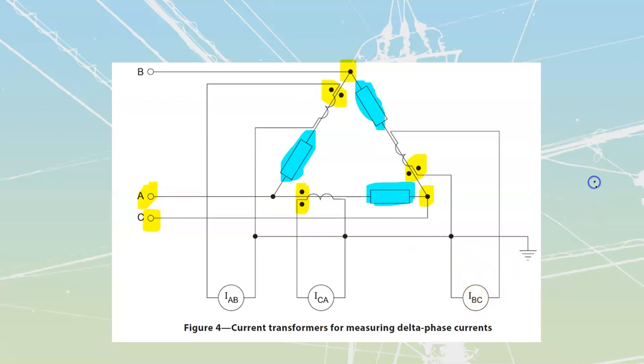This doesn't make any difference to us that it's connected into a Y type of configuration, because if I look at the individual meter loop, it's just reading what's inside here, and we're not even looking at voltage. Voltage is the thing that changes from delta to Y when we're going across. At this point, we're just looking at current going through these.